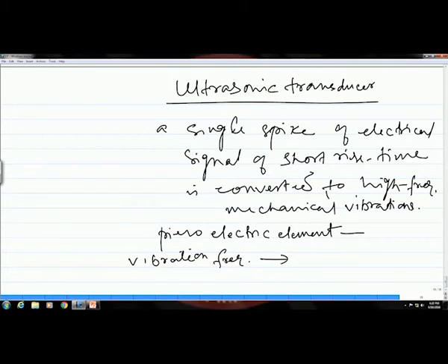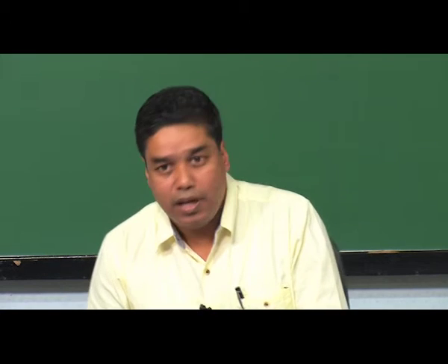Okay, so, it vibrates with a wavelength which is twice the thickness of the element. So, that means for higher frequency the thickness has to be lower. Lower the thickness, higher will be the frequency.